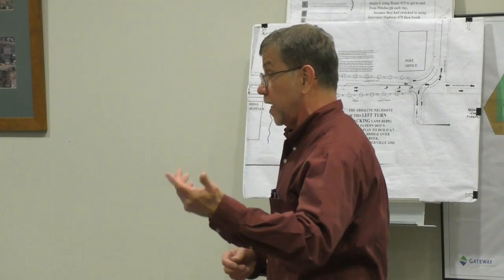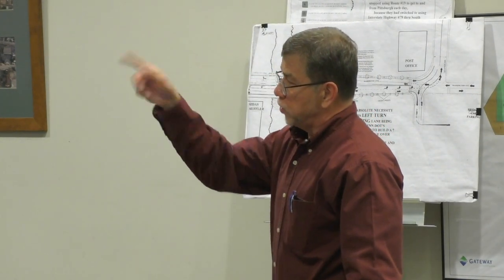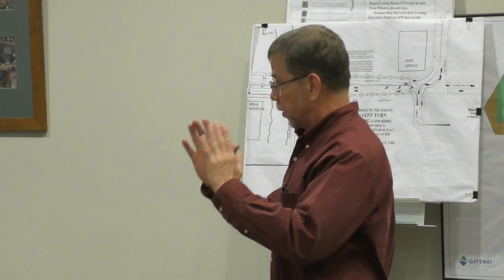I was on a site for the Wisconsin Central many years ago, which is now being purchased by Canadian National. We were in one of those silver signal buildings, and they had a lightning protection device up on the main breaker panel. I said to the guy, do you know if you've got things working? He said, I have no idea. I said, have one of your maintainers take it off the panel, let's crack it open right here. They took a screwdriver, the thing was sealed with epoxy — took a hammer and screwdriver and popped it off. The thing was pure charcoal, burned to a crisp inside. The chief engineer looked at it and said, I wonder how many of these we have out there like this. I said, it's not doing any good. He said, how is yours better? Way more energy it can handle. We advertise the protection that you can see, because you can look right at the parts and know right away if the parts are burned.